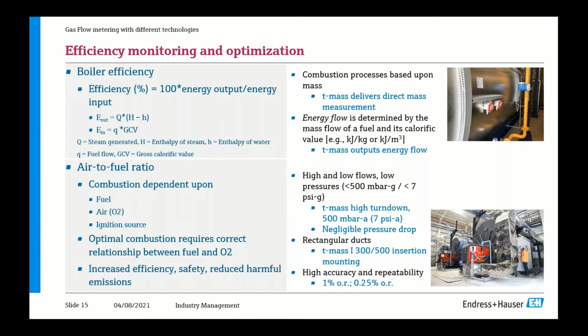Boiler efficiency is a very important indicator, something that should be monitored in real time because it gives an idea about the performance of the boiler. And this may change over time. If there is a reduction in the boiler efficiency, it could be an indication that there is a need for maybe a repair of the boiler or possibly maintenance of the boiler of some kind. For this purpose, the thermal mass can be used for measuring the natural gas because the whole combustion process does deal with mass. The T-mass, or thermal mass, is very ideally suited for this purpose because it does, like the Coriolis, deliver a direct mass measurement.